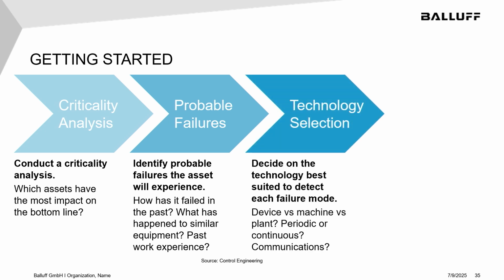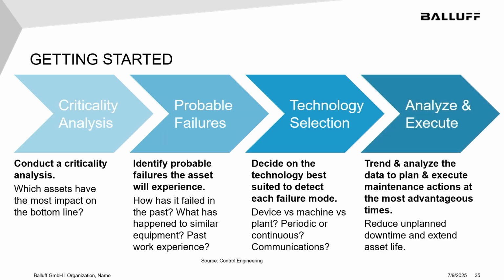Then identify the technology. Do you want to measure vibration and temperature? Do you want to take that data out of those sensors directly into your control system, or do you need an edge gateway device? What's the best approach? Do you want to take a condition monitoring as a service approach, have somebody else do it, or do you want to keep control of the data and the equipment? And then finally, install, analyze, test, and make sure you're monitoring the right things. Are you now starting to see the data and the signals show you that a potential failure is occurring and that you're able to prevent those failures, or do you need to refine and start monitoring other pieces of the equipment, gather other signals? And then you can repeat the cycle and expand.